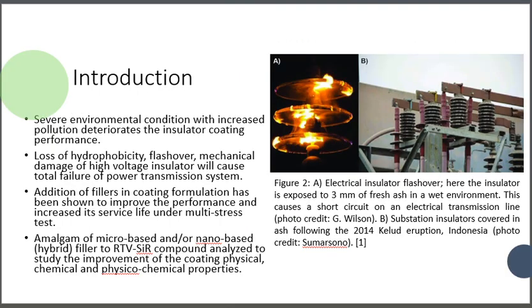Despite these advantages, severe environmental conditions can significantly reduce the performance of insulator coatings. In regions with high pollution levels such as coastal, industrial, or volcanic areas, contaminants accumulate on the insulator surfaces. This contamination can lead to loss of hydrophobicity, surface leakage currents, electrical flashover, and mechanical degradation of the insulator. These failures may ultimately lead to power transmission interruptions. To overcome this issue, researchers have investigated the addition of fillers to RTV-SiR coatings. In particular, combining micro-based and nano-based fillers, such as hybrid fillers, has shown promising potential to improve the coating's physical, chemical, and physico-chemical properties.